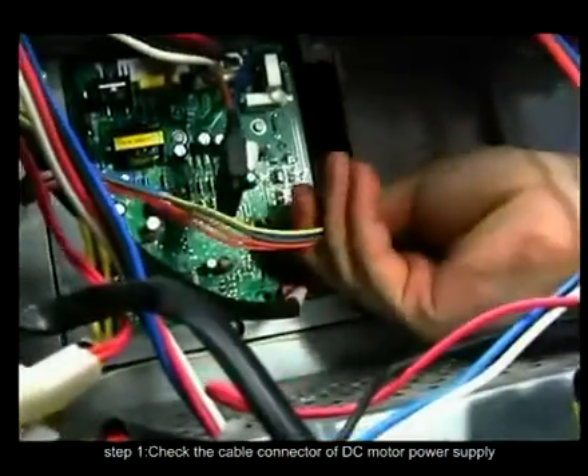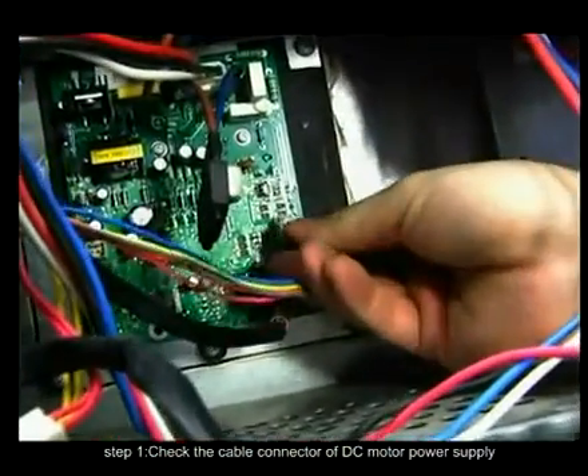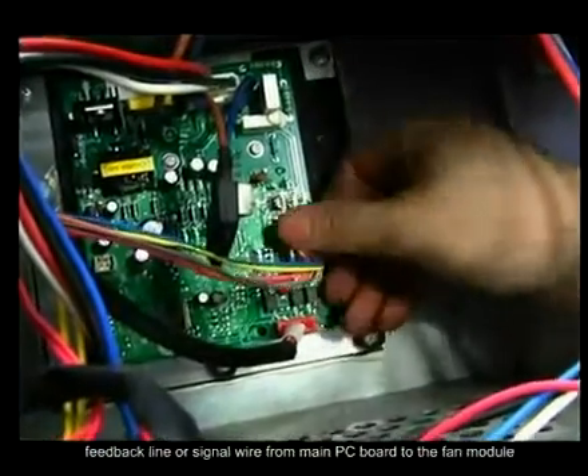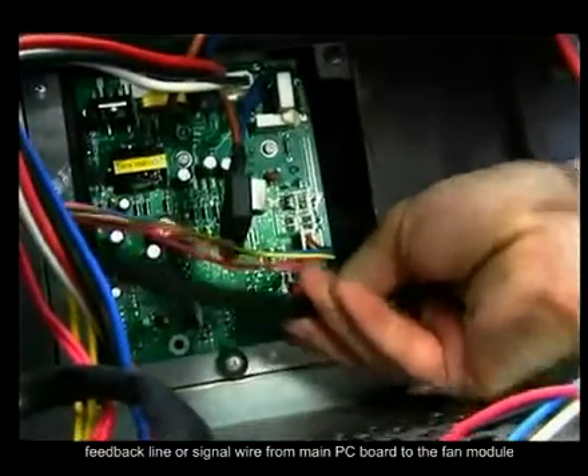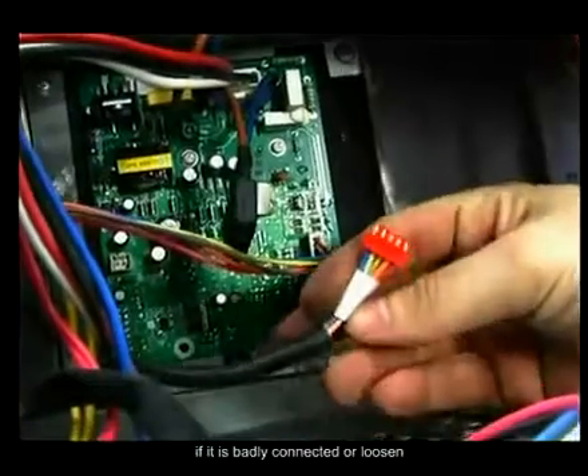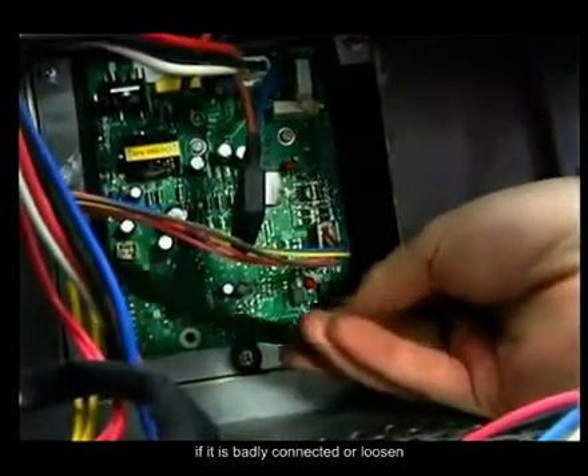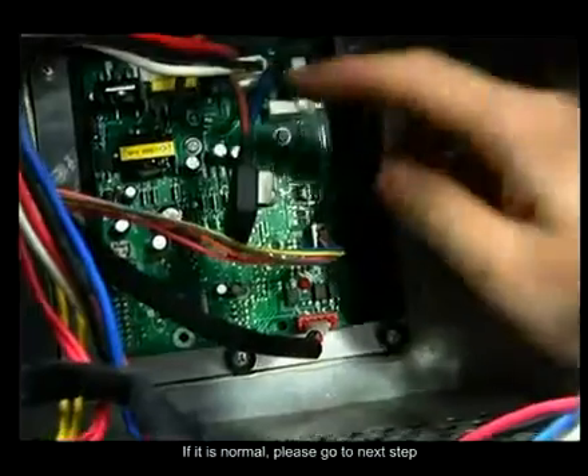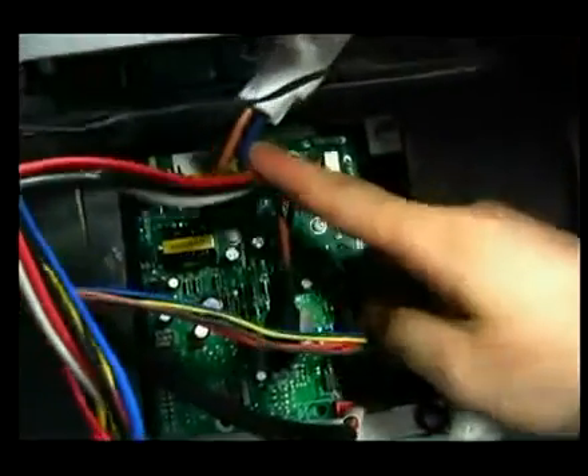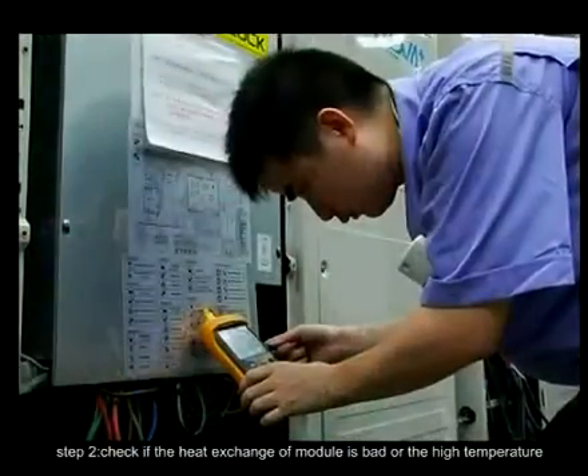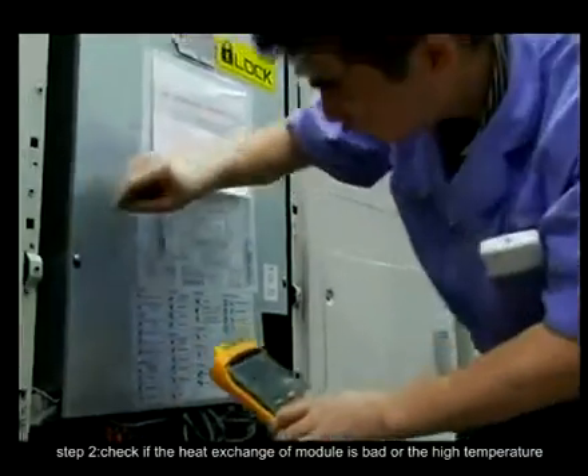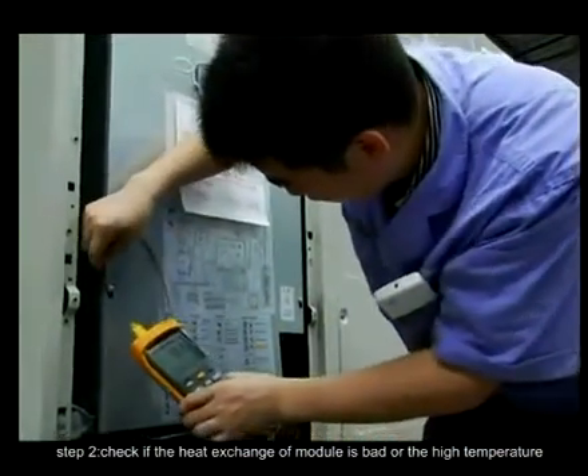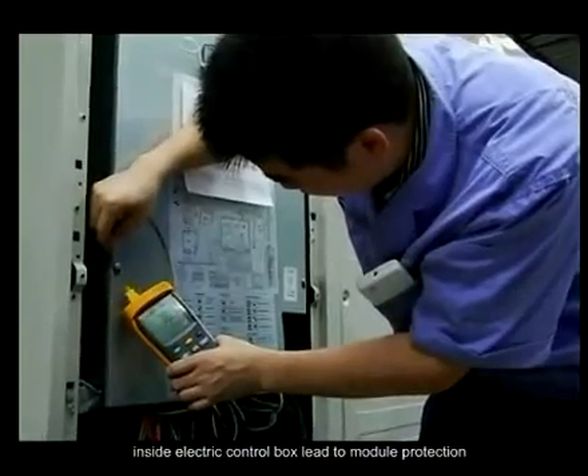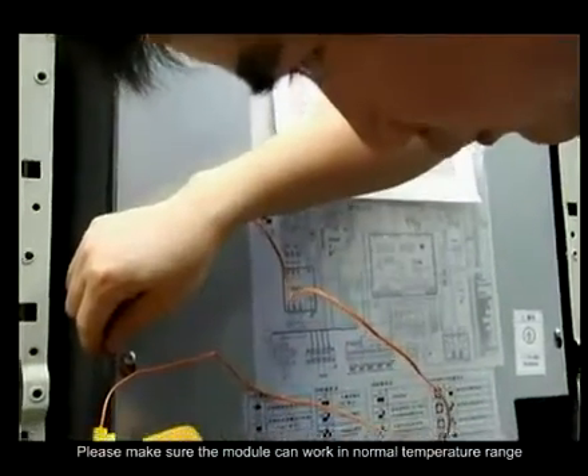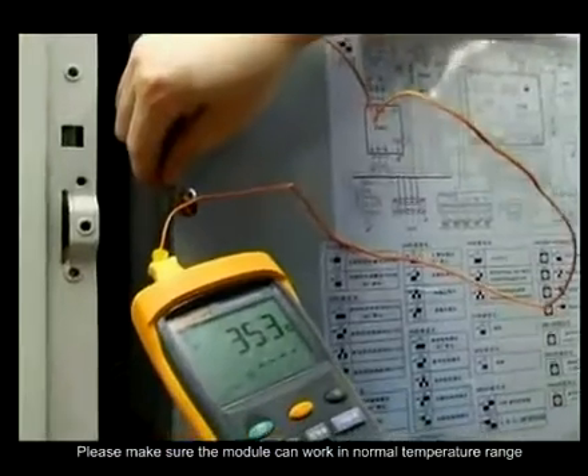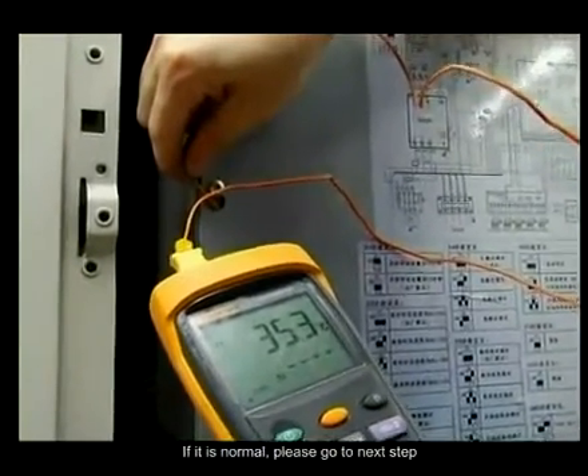Step 1. Check the cable connector of the DC motor power supply, feedback line or signal wire from the main PC board to the fan module, and whether it is badly connected or loosened. If it is normal, please go to the next step. Step 2. Check if bad heat exchange of the module or high temperature inside the electric control box leads to module protection. Please make sure the module can work in the normal temperature range. If it is normal, please go to the next step.